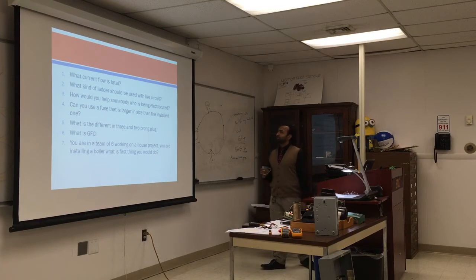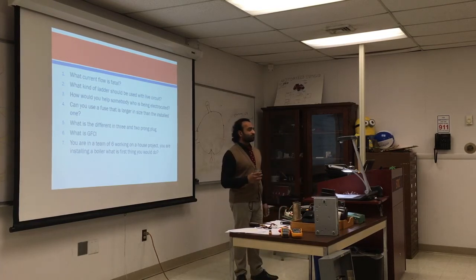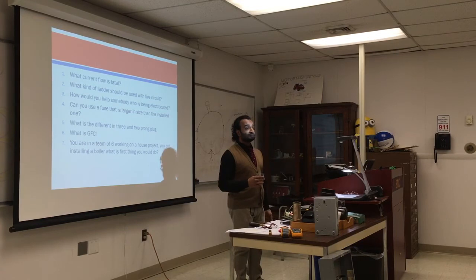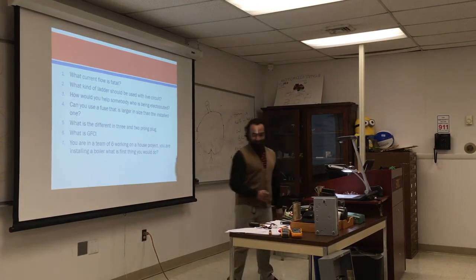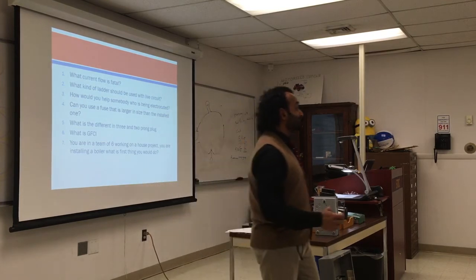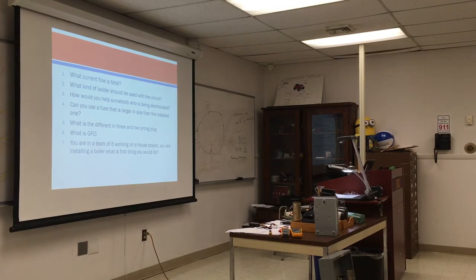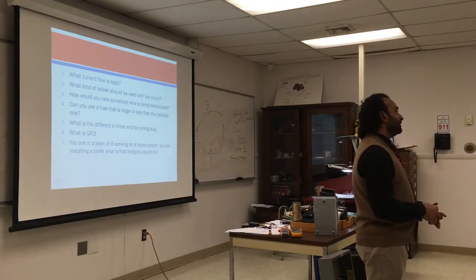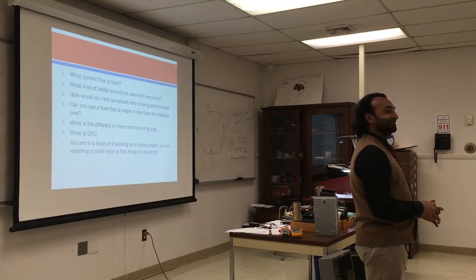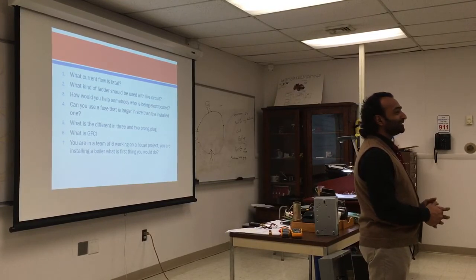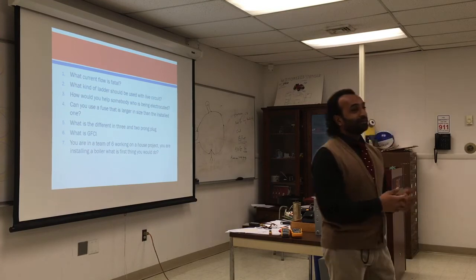Can you use a fuse that is larger in size than what's installed? Say it's rated 1.5 amps - can you put in a 2 amp? You can, but you shouldn't. Same thing with circuit breakers - if it says 15, you shouldn't put in a 20. People do it anyway because the fuse keeps tripping, so they go buy a 20 instead of 15 to stop it from tripping. That's stupid - it treats the symptom, not the problem. There's a reason it's rated 15 amps. Don't do that, it's a safety issue.